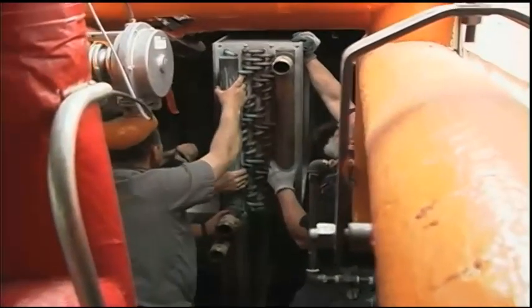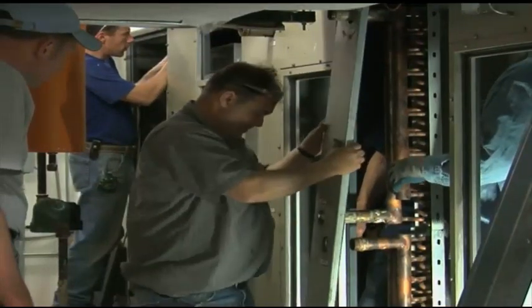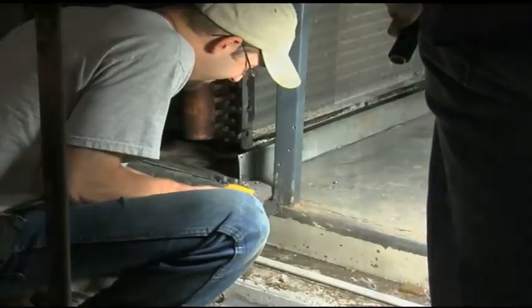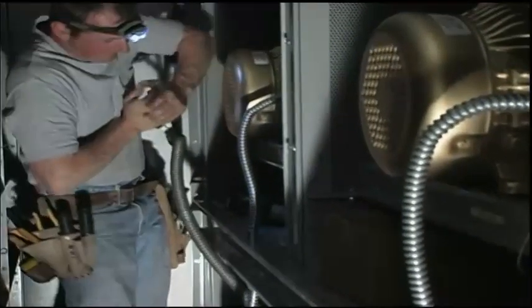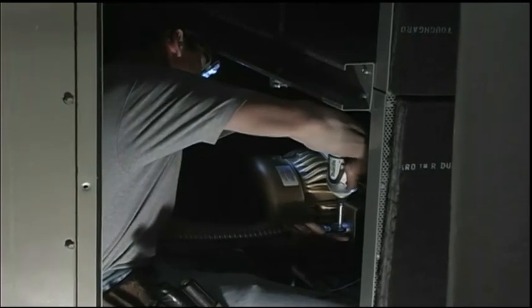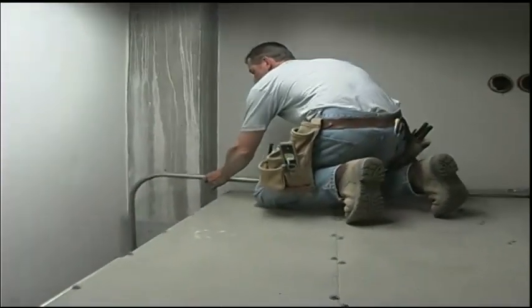Meanwhile, work on relocating the coils in the drain pan was completed, and these were reconnected to chilled water and condensate drain piping. The sidewall struts on the air handler were re-welded, and in some cases relocated to simplify service access in the future. While the air handler's structure was being reassembled, electricians extended electrical service and control wiring to the units. The units themselves were pre-wired, simplifying this task. Electrical conduit was installed atop the air handler and dropped down to the four units. The amount of space required downstream and upstream of the fan wall cells is often dictated by what's necessary for service access.